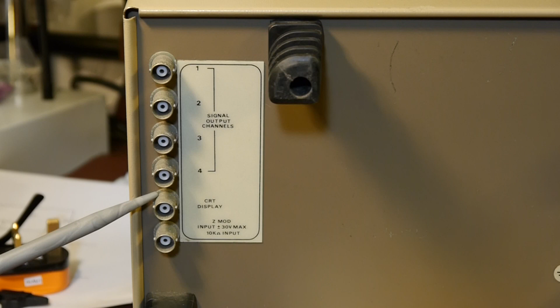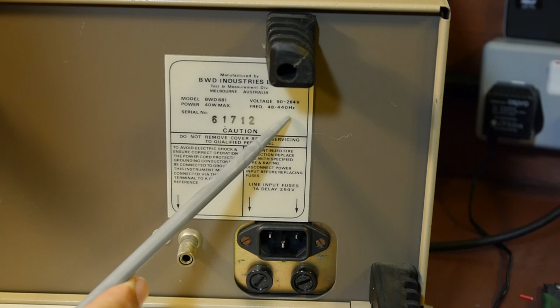On the other side of the panel we've got the mains input, and the equipment will work between 90 volts and 264 volts AC, with a frequency range between 48 and 440 hertz, which seems like quite a wide range - in fact a very wide range. I think the reason they go to that upper extreme of 440 hertz is because a lot of aviation equipment uses high frequency rather than 50 hertz, to keep the losses in the transformers down and keep them as light and compact as possible. So if you're working on an aircraft, you're probably working at higher frequencies.